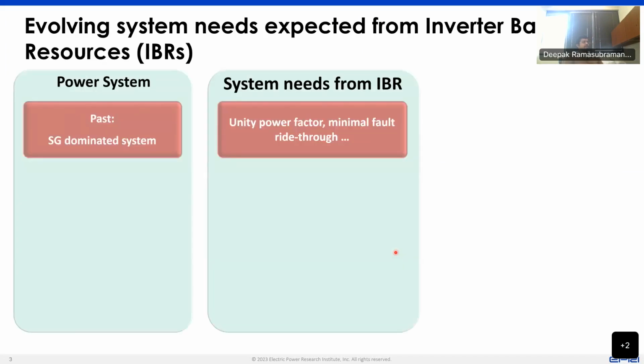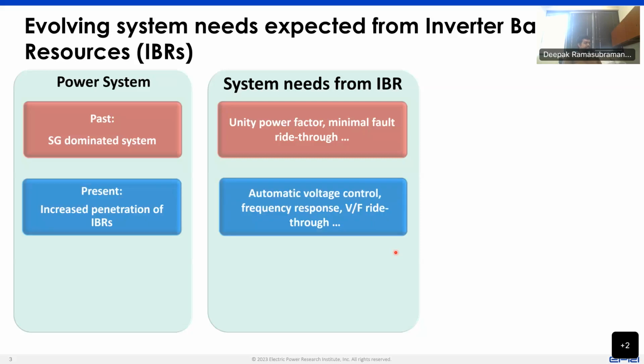So as we move towards a system with more inverter-based resources, it is helpful to take a look at the kind of needs and how those needs evolve across our network. In the past, the power system that we've had is synchronous generator dominated. At that point in time, we essentially wanted the inverter-based resources to operate at unity power factor, with minimum fault ride-through, and not really provide any further associated services to the network, because there were a lot of synchronous generators in the system that could provide the needs of the network.